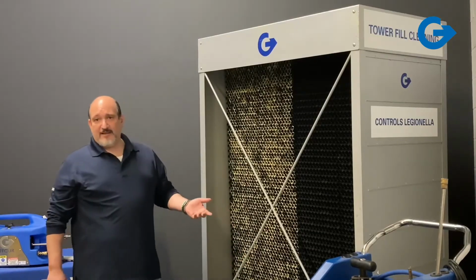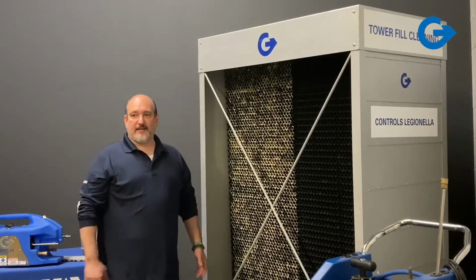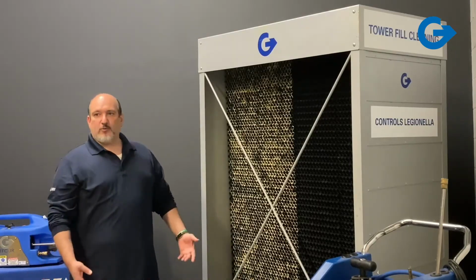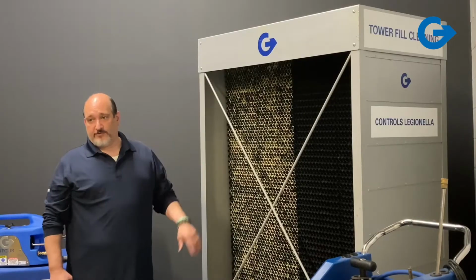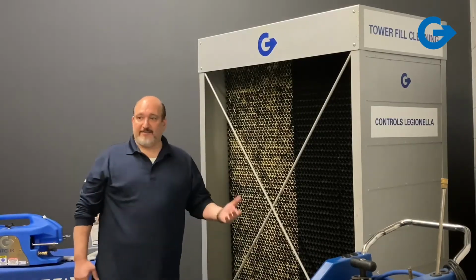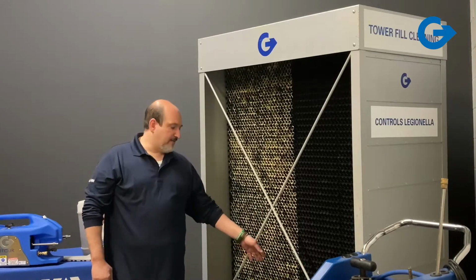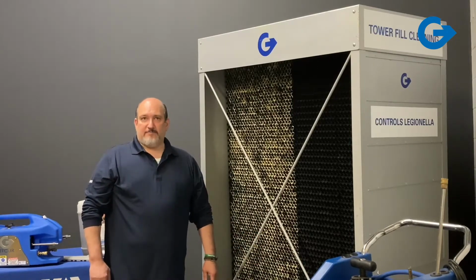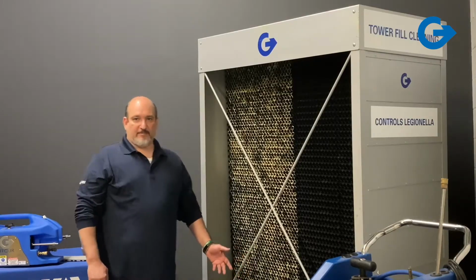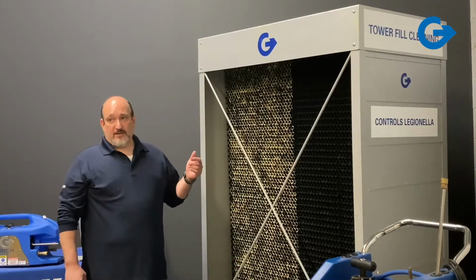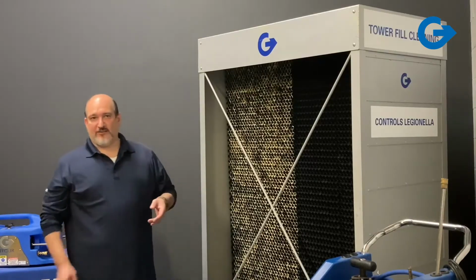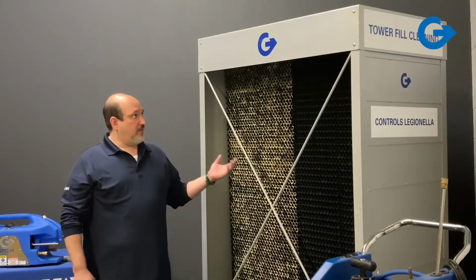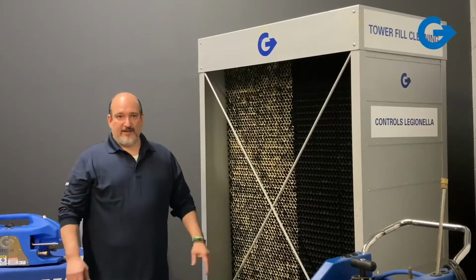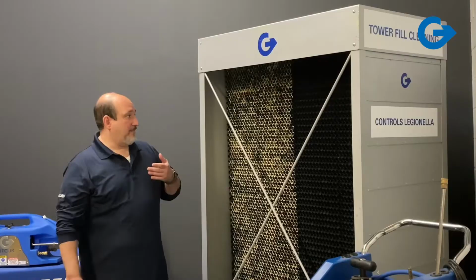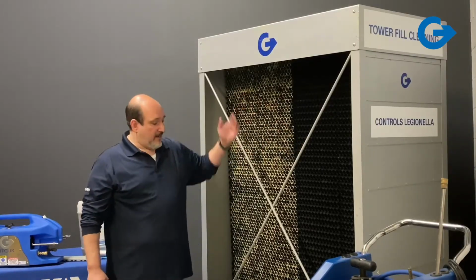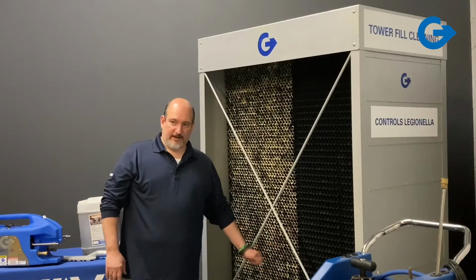In the basin you have all that sediment and mud that collects over time, depending on where you are and how high or low your cooling towers are. You might get all different types of deposits ending up in the basin of the tower, anything from leaves, cottonwood, sometimes cicadas, to a heavy sludge if you're in a city environment where your cooling tower is acting like a filter for the whole city. All that smog and air being sucked into the fill and through the water leaves deposits that collect down here.